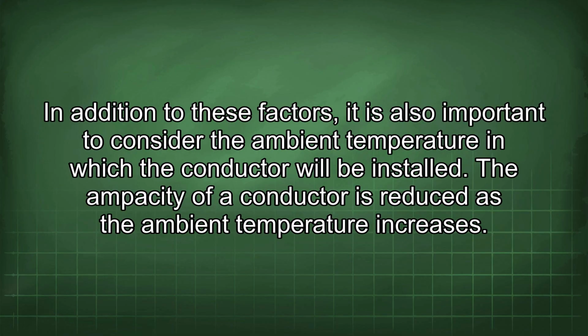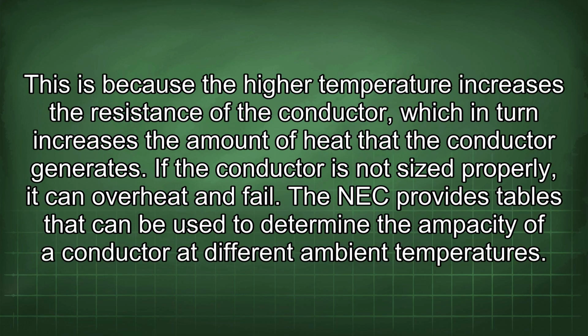In addition to these factors, it is also important to consider the ambient temperature in which the conductor will be installed. The ampacity of a conductor is reduced as the ambient temperature increases. This is because the higher temperature increases the resistance of the conductor, which in turn increases the amount of heat that the conductor generates. If the conductor is not sized properly, it can overheat and fail. The NEC provides tables that can be used to determine the ampacity of a conductor at different ambient temperatures.